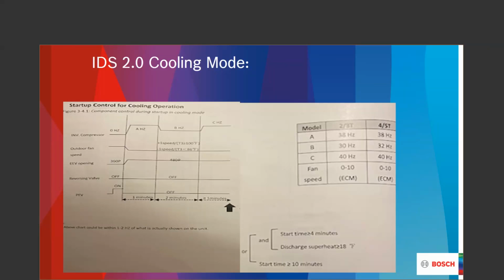And so what we're looking at here is a ready-now-to-work piece of equipment. We have L1 and L2 voltage, and we get a call for a compressor to come on. When the compressor comes on, we are up here now in what they call the A hertz rating. If we move over here to this particular diagram, we see that the A represents right around 38 hertz, whether it's a 2, 3, 4, or 5 ton piece of equipment. So this particular range is going to be 38 hertz on the 2.0. That 38 hertz is going to be there for 1 minute.